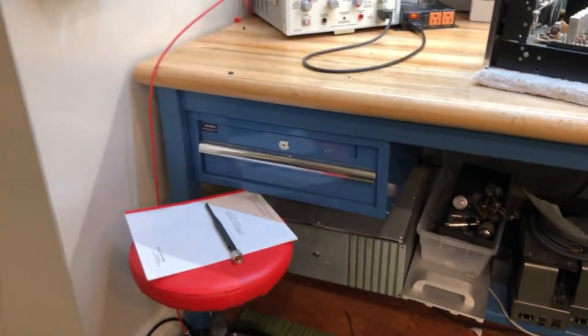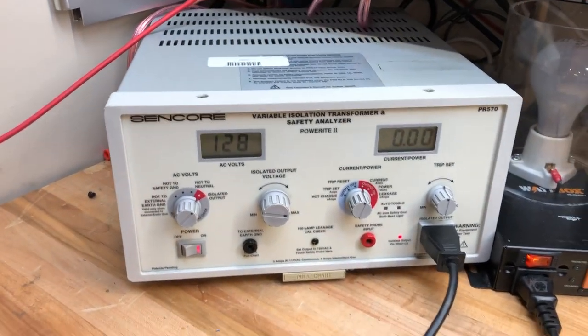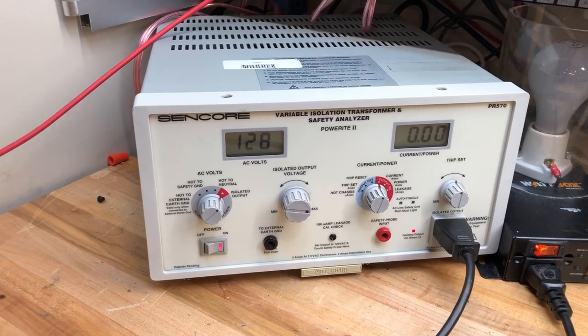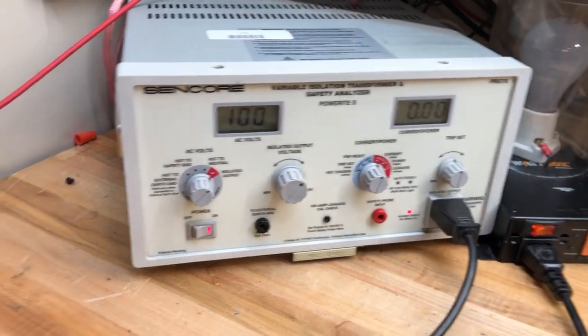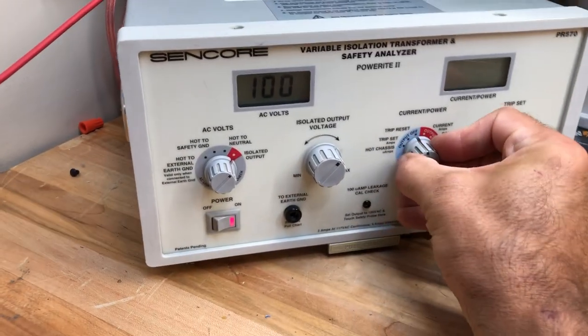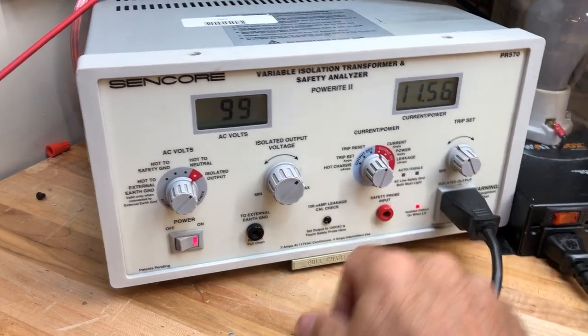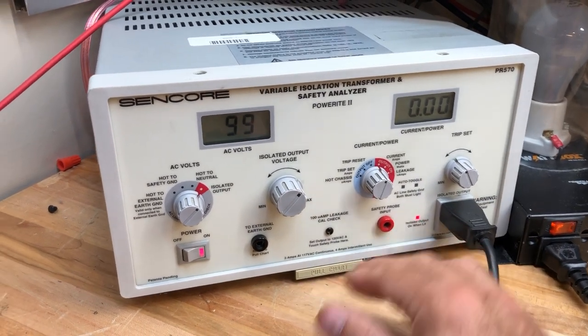Let me do a deeper dive into each of the components and how we arrived at them. Starting from the power side — this just arrived recently. It's our Sencore Powerite PR570, an isolation transformer both for safety of us and safety of the equipment. It allows us to dial in the voltage carefully and set current limits, so that if we're testing, for example, this MAC 1700 or 1900 preamp, we can put a limit on how much current it's going to draw before it trips.